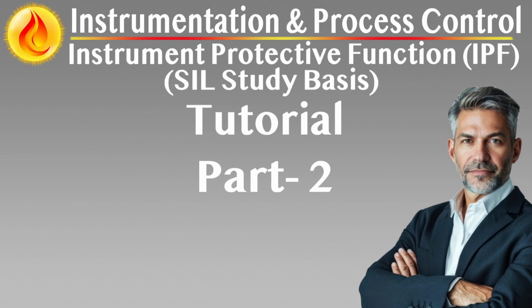Initiation point: the moment a deviation begins, e.g. pressure buildup, level rise, temperature increase. Trip point: the threshold at which the IPF should activate to prevent escalation. Response deadline: the point beyond which process conditions become irreversible, unsafe, or destructive. PST is measured from the initiation point to the response deadline, not from when the IPF receives a signal. This includes detection time, signal transmission, logic execution, final element actuation, and process stabilization.